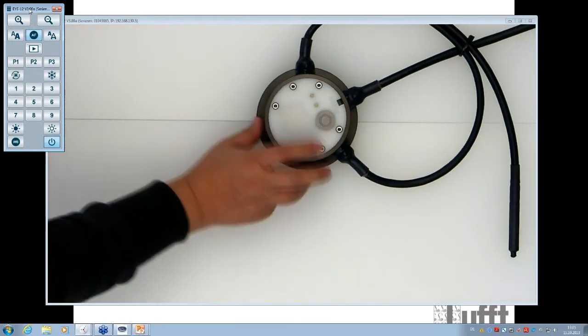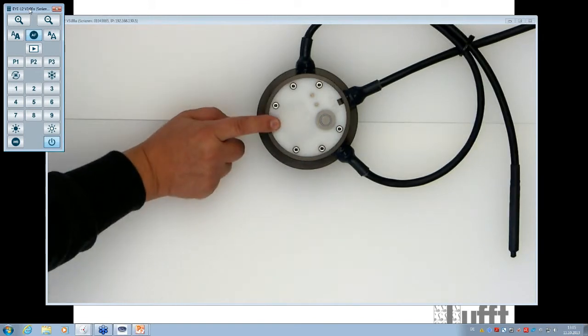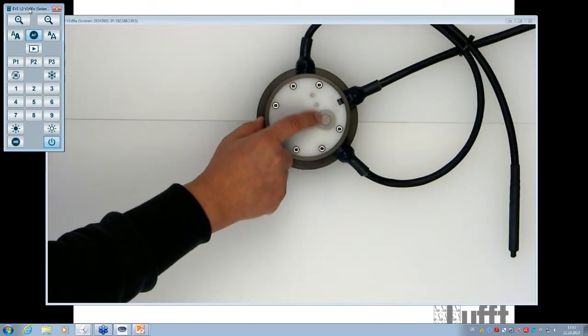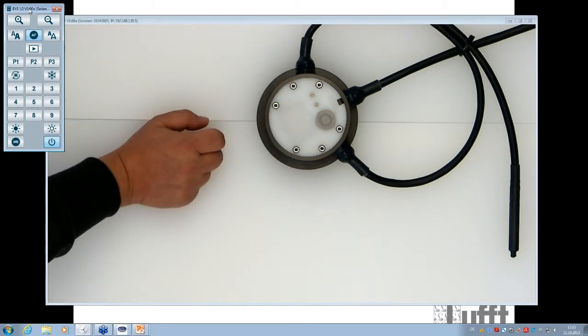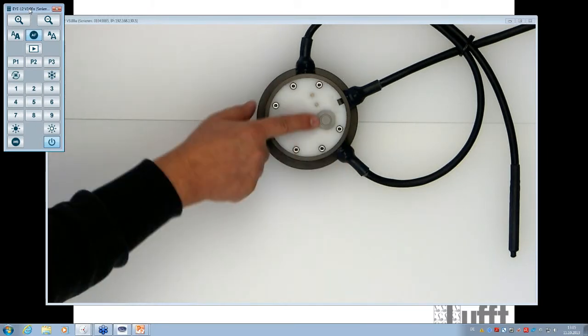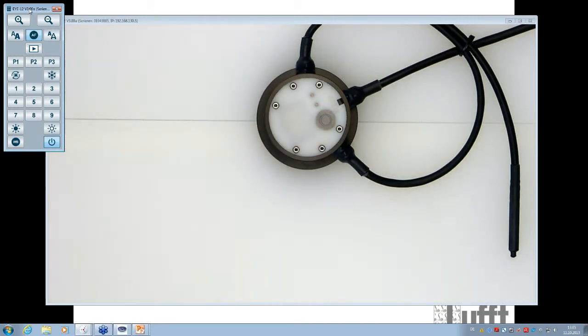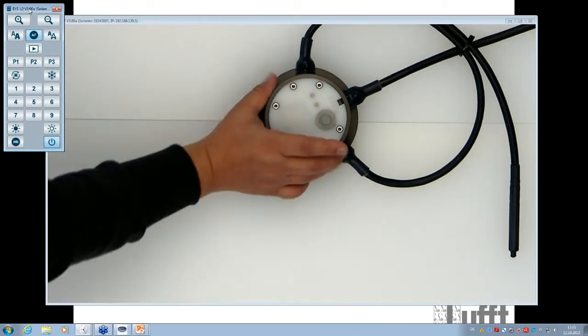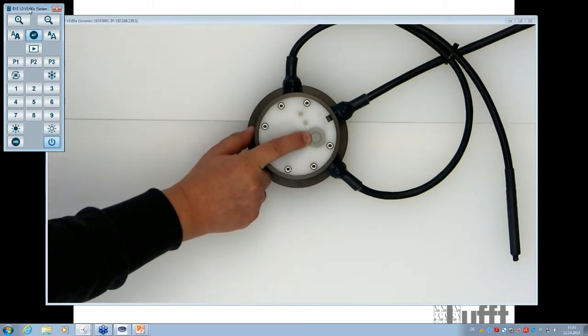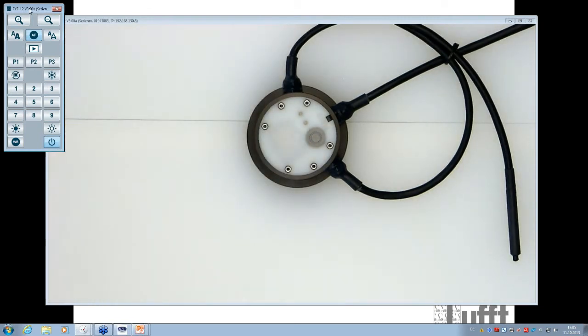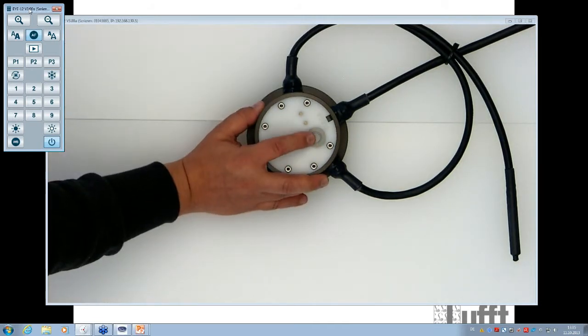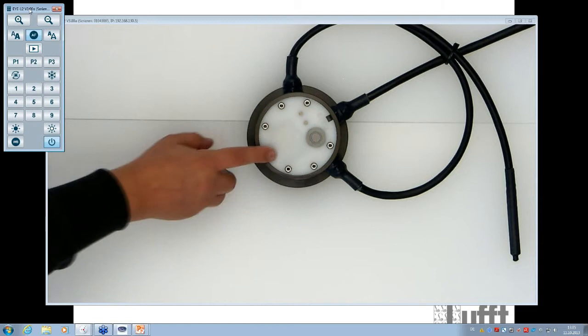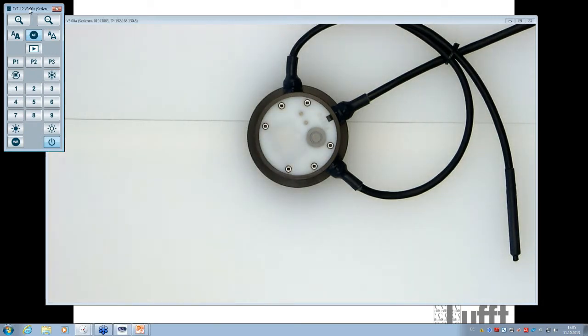So in this case, the radar sensor will be activated only if here between the two electrodes we will have some liquid, some water. Because it's a capacity measurement here, and if it's dry it has a special capacity value, and if it's wet or damp it will change the capacity. So that means if the capacity will change to damp or wet here, the radar sensor will start to measure. So that's really important to know if you want to do the calibration on site later. So that's the first measurement here, which I want to explain to you.